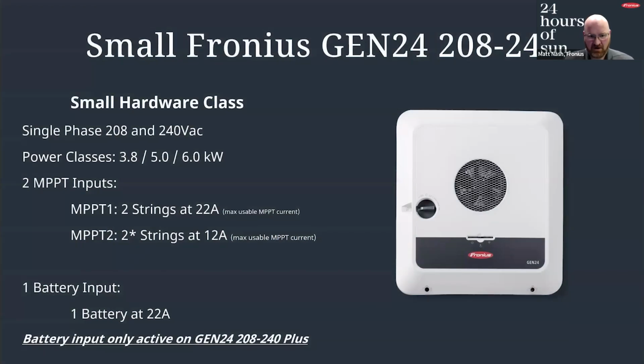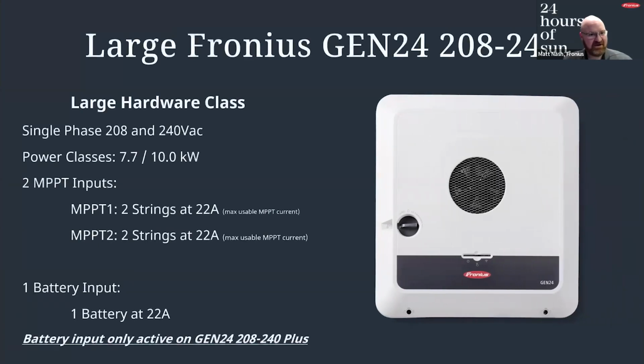So we'll go ahead and talk about the small hardware class. These are the 3.8, 5, and 6 kilowatt inverters. They can handle up to 22 amps of usable input current on the first tracker and 12 amps on the second. There are 2 inputs, but with the high power modules that are in the market now, 1 string is probably going to be all you're going to realize. And of course, we talked about the battery input at 22 amps, and that's only active in the Plus model. We also have a large hardware class, which is physically just a little bit bigger, but it offers 7.7 and 10 kilowatt output. And they have 22 amps of usable current on both trackers.